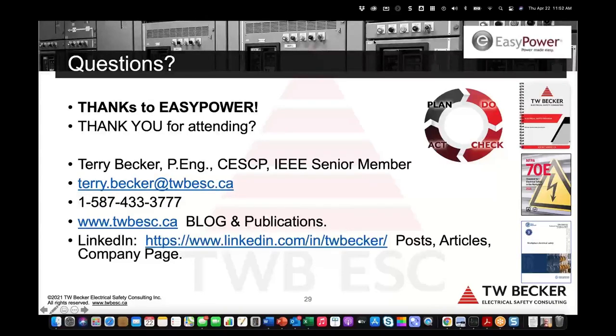70E and Z462 say every 5 years, you should review your studies. And if things have changed in the power system, then update your study or the portion of the study that's impacted. What we've had happen is new formulas came out. But like I said, it doesn't discredit your existing calculations, because the results for VCB and VCBB in the new formulas will be relatively the same, if not slightly lower for VCB. So you really just have to do this risk assessment to prioritize what studies to budget for and then schedule to update the calculations.